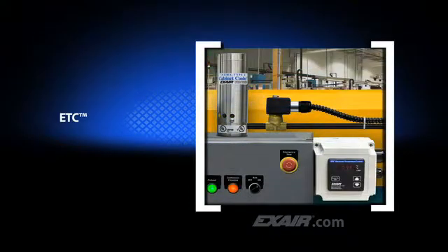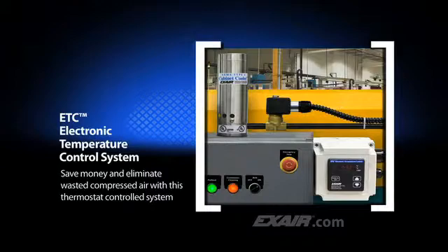If you prefer digital temperature control, EXAIR has the ETC, Electronic Temperature Control. This controller can accurately maintain a constant temperature that is slightly under the maximum rating of the electronics. It permits just enough cooling for the electronics, without going so cold as to waste compressed air.